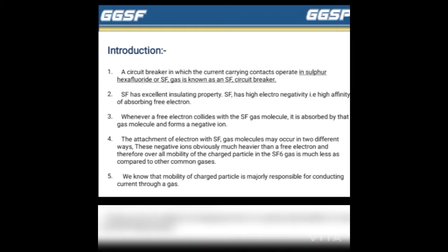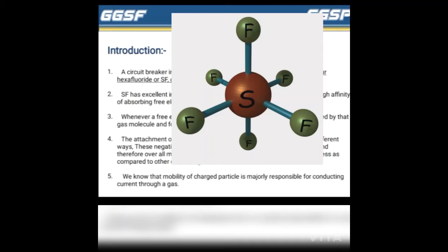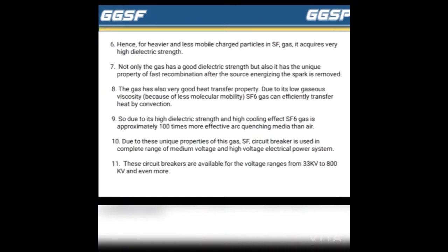These negative ions are obviously much heavier than free electrons, and therefore the overall mobility of the charged particles in SF6 gas is much less compared to common gases. We know that mobility of the charged particle is majorly responsible for conducting current through a gas. Hence, with heavier and less mobile charged particles, SF6 gas acquires very high dielectric strength.